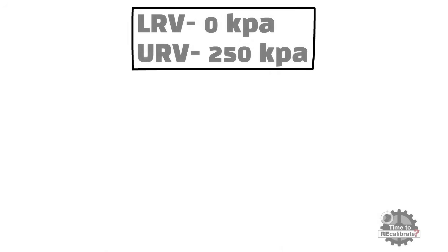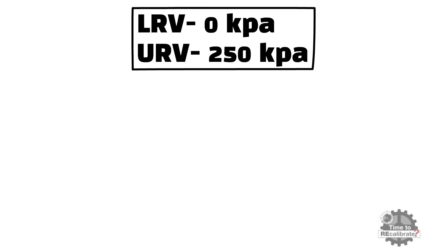Now you should have a lower range value and upper range value in order to perform a 5-point verification test. You can also get this value by connecting a HART instrument in series with the pressure transmitter. In this example, the lower range value is 0 kPa and the upper range value is 250 kPa.